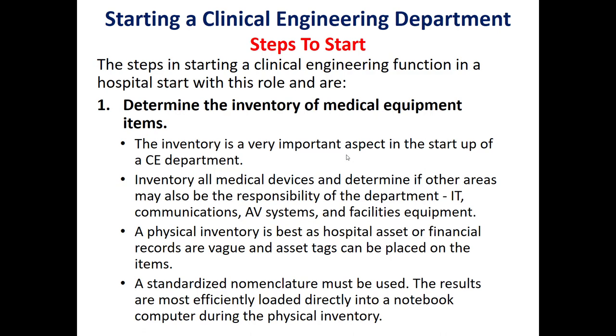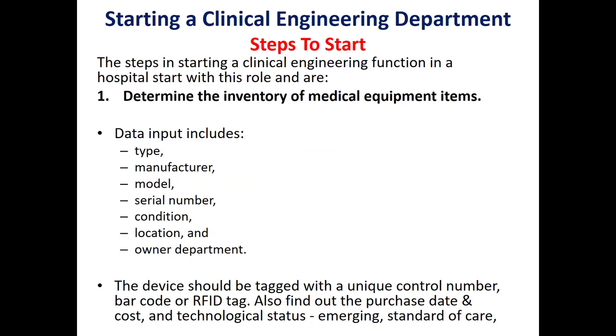A physical inventory is best; we should use a tagging system and standardized nomenclature. We should include data for each device, such as the type, manufacturer, model, serial number, condition, location, and owner department. Each device should be tagged with a unique control number — a barcode or an RFID tag, which stands for radio frequency identification. We should also include the purchase date, cost, and so on.